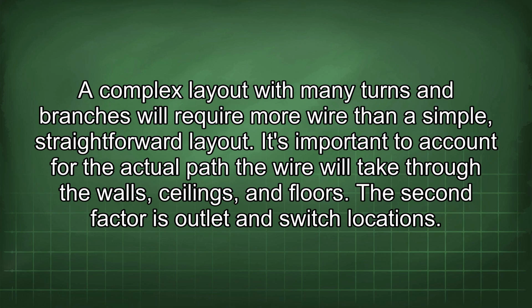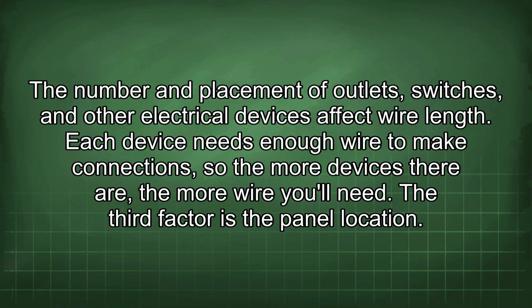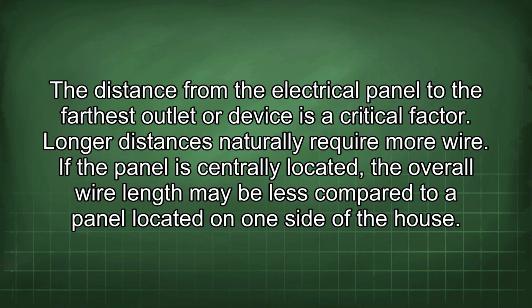The second factor is outlet and switch locations. The number and placement of outlets, switches, and other electrical devices affect wire length. Each device needs enough wire to make connections, so the more devices there are, the more wire you will need. The third factor is the panel location. The distance from the electrical panel to the farthest outlet or device is a critical factor. Longer distances naturally require more wire.